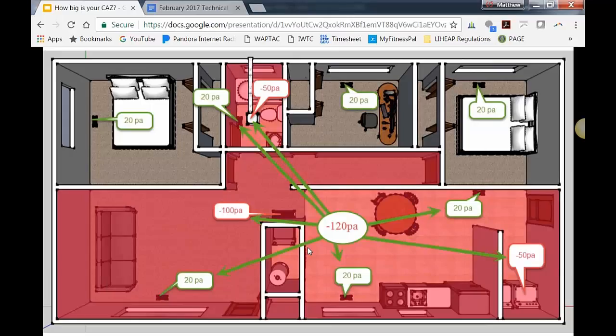I don't think we've given any direction on that at all, but your point is correct. If there is an air conditioner in a bedroom and we're doing a CAZ depressurization test, and under normal conditions that is open, that should probably be left open. Your point is valid, Tony. Yes, in wintertime conditions, those things are probably normally closed somehow. I'm just pointing out there are those weird things you run into.